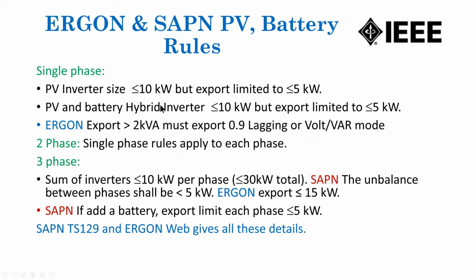There are some rules on this, and as time goes on, these rules are becoming tighter in order to prevent the duck curve getting too bad. So at the moment, if you've got a house with single phase or 2 phases, then the PV inverter size should be less than 10 kilowatt. On a 10 kilowatt inverter, you can have 30% more solar panels, so you can have 13 kilowatt of solar panels on a 10 kilowatt inverter, but you must export limit this to less than 5 kilowatt. So you're not allowed to export more than 5 kilowatt.